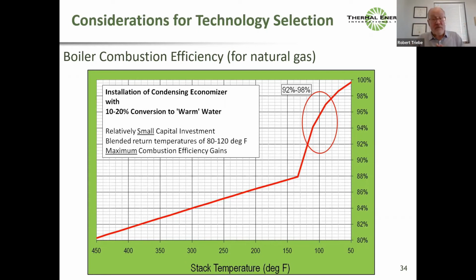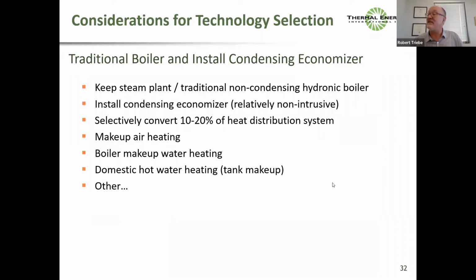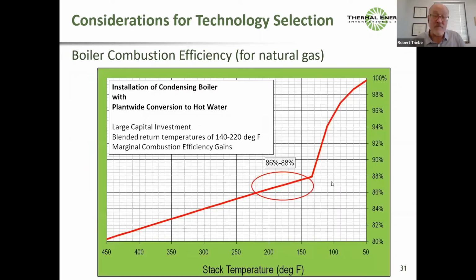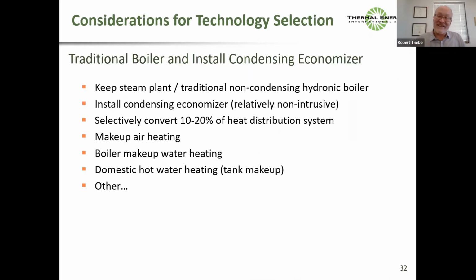All right, but the big picture is, by separating cold and hot users, even in a hydronic circuit, your efficiency with the exact same system has gone up not 1 or 2%. Those 40 degrees are in that critical curve. Because we're heating the cold sink separate from the hot sink, it doesn't give us 1 or 2% difference. It gives us 5 to 10% difference just by hooking up the sinks differently, separately with the boiler. So that's an integration consideration that I've almost never seen in the field.